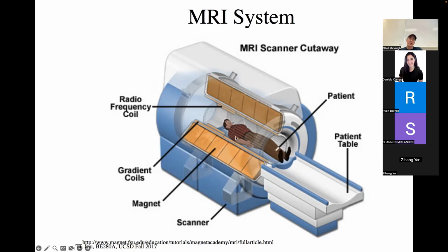And it's provided by coils that are wrapped around the patient, and those coils have electrical current in them. They are bathed in liquid helium such that the material that the windings are made of goes into a superconducting mode. So there is no loss or heating with that current. And once you get them down to the superconducting temperature, you ramp up the current, and then you switch it shut, taking your voltage generator off, and it just keeps going, right?